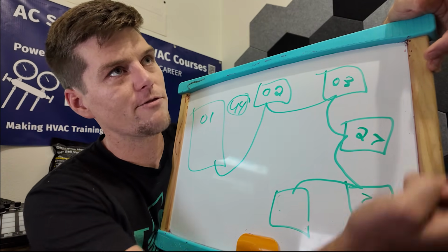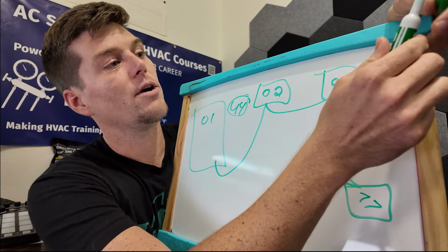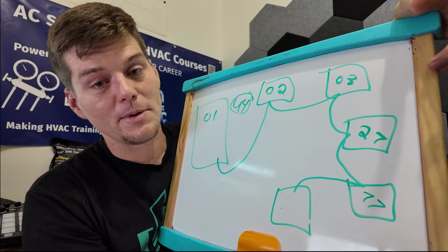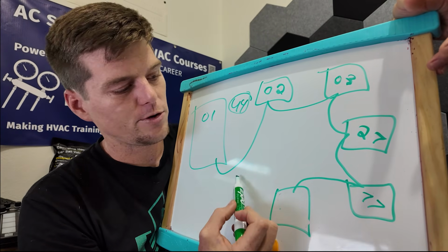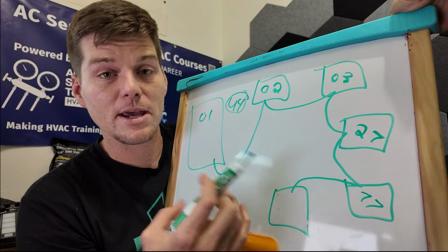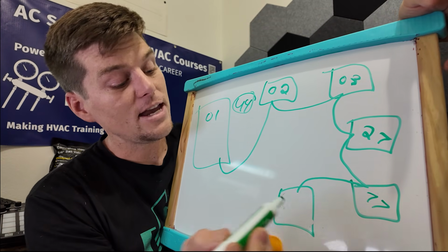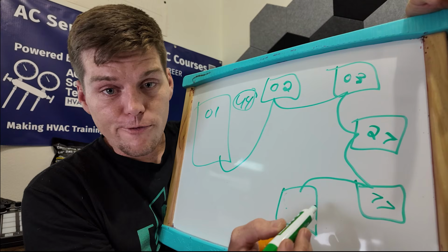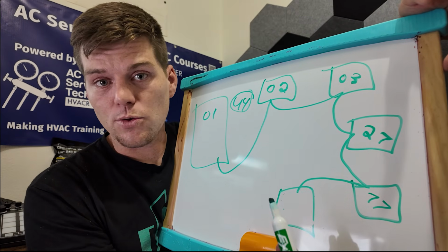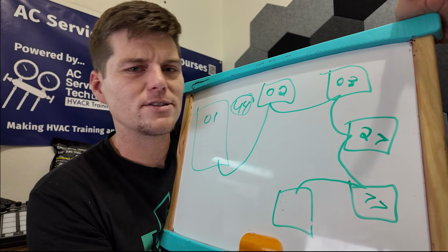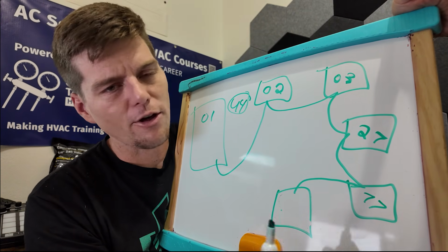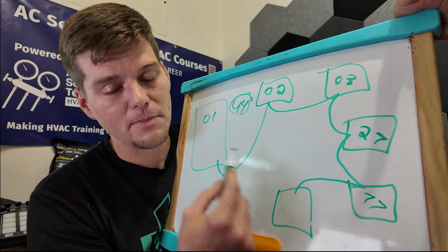Now you're saying I have to go through every single disconnect to make sure that everything has power. Well, no, the first step, in my opinion, would be to go to the outdoor unit, obviously verify the error code is still a U4 at the outdoor unit, that it's not masking the error code. And when we say masking error codes, it means that the indoor units are showing a U4, but the outdoor unit is showing an E2, right? And under that E2, maybe there is an E4, right? Or maybe it blew a fuse and now it's not communicating correctly. These are all things that we have to check, make sure that the error codes match up.